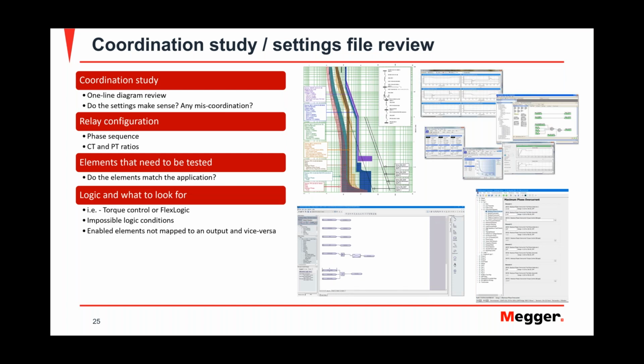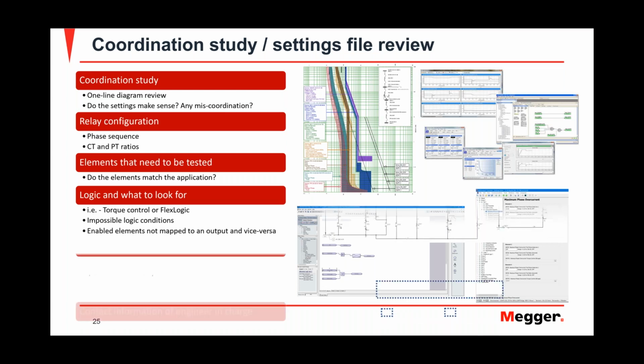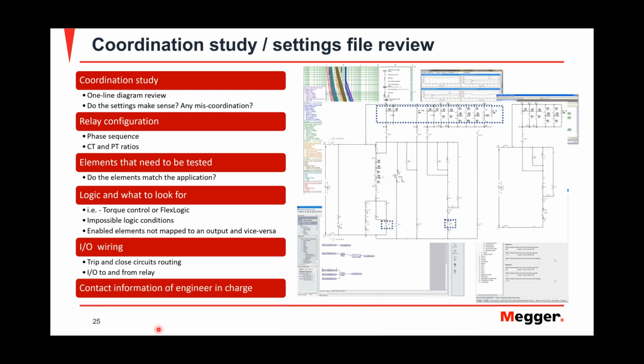When you look at the logic, either your torque control or your FlexLogic or whatever the logic is called for the particular relay, are there any impossible conditions? Are there any elements that are not mapped to an output, or an output that's not mapped to an element that's enabled? Things like that you could do before you even show up to the site.